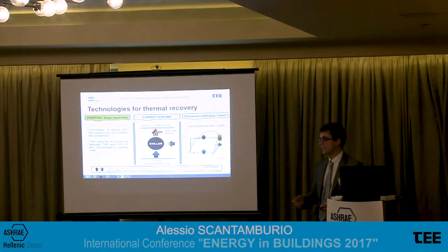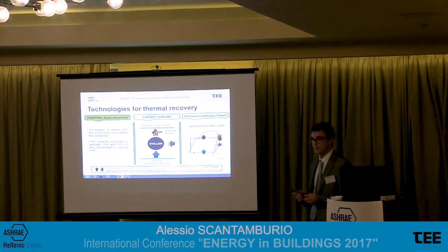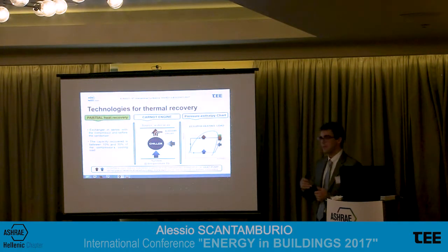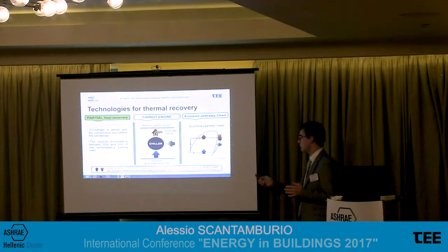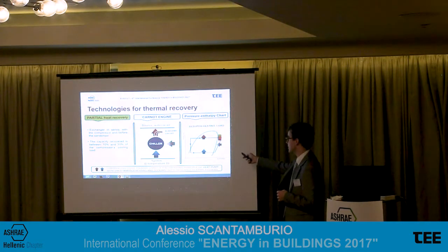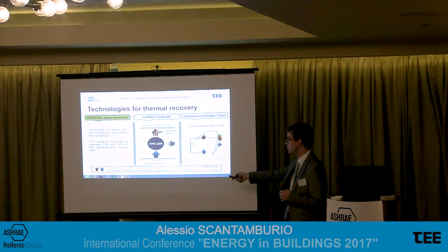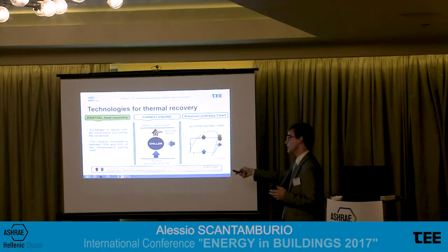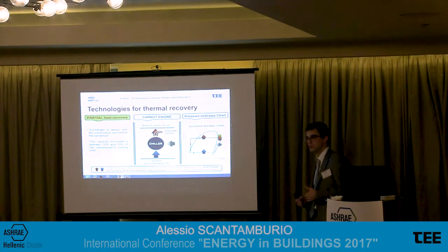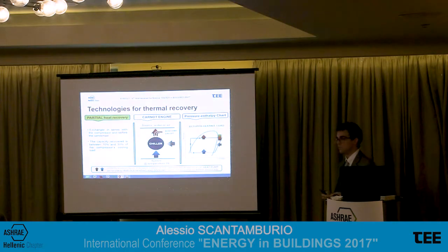How is it possible? Let's have a look at partial heat recovery technology. Partial heat recovery has an additional exchanger placed after the compressor, and with this technology we are able to recover a certain part of the superheating load. So while the chiller is producing cold water, we are able to recover a certain amount of hot water in an auxiliary circuit. In this case, it is between 10 and 30%, more or less, depending on the conditions, of the compressor's cooling load.